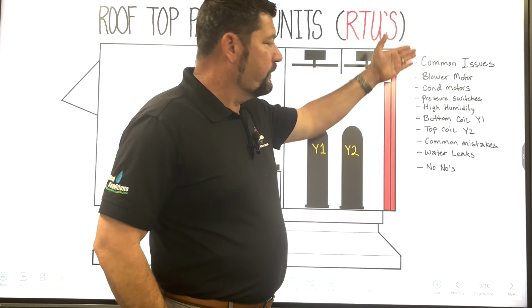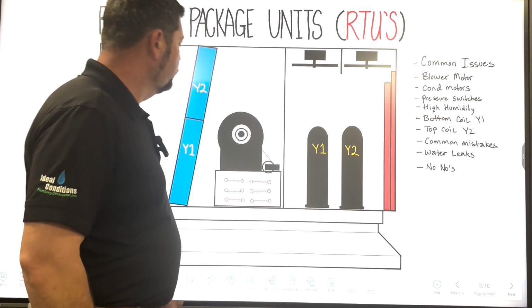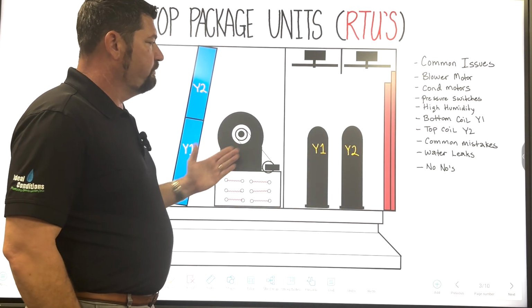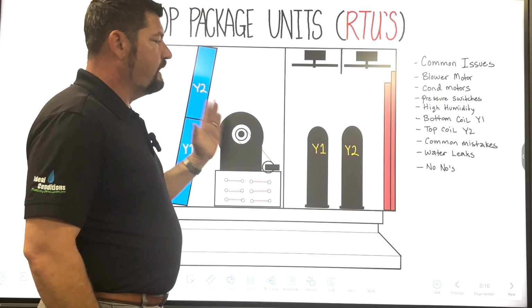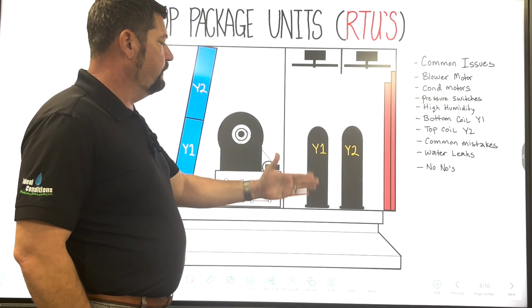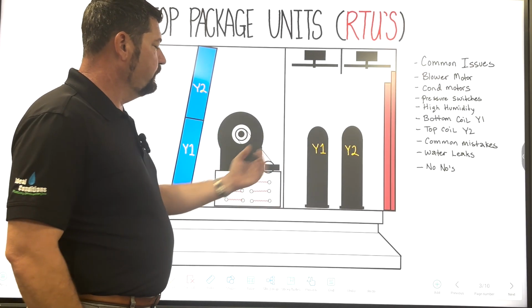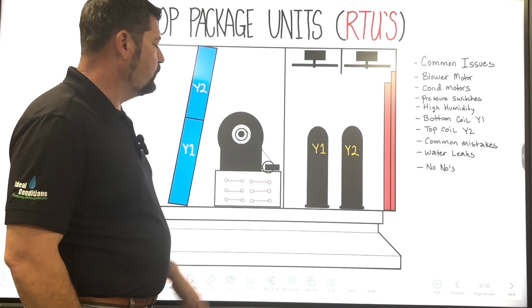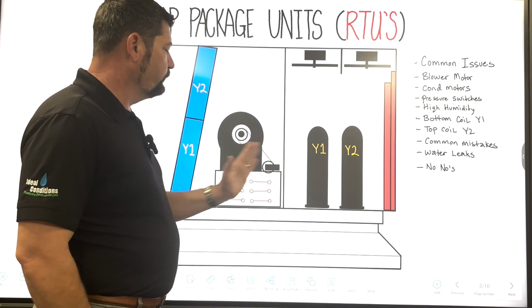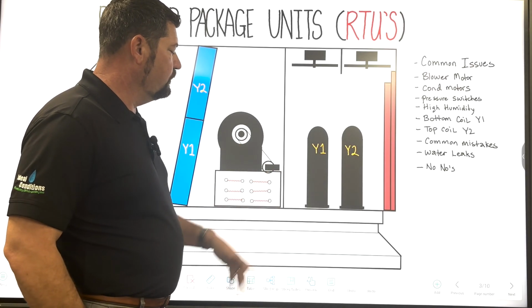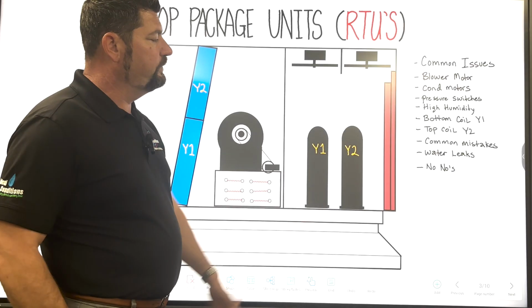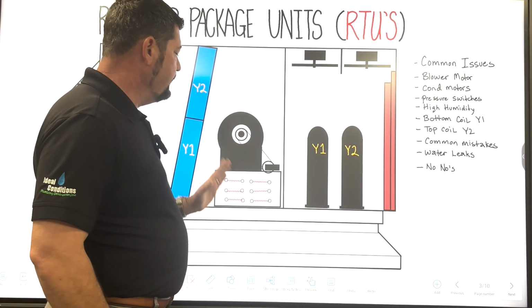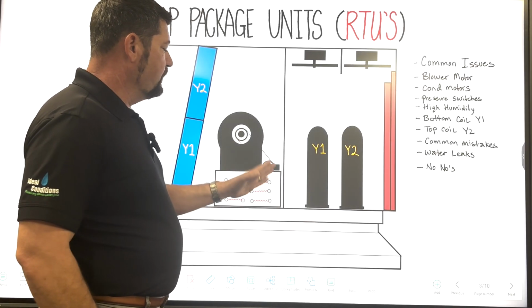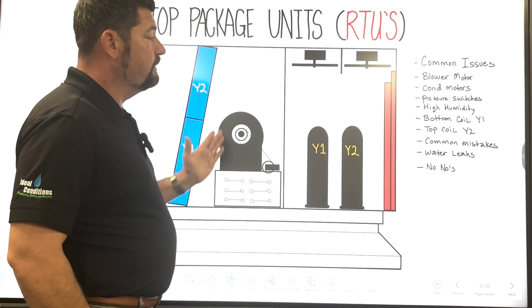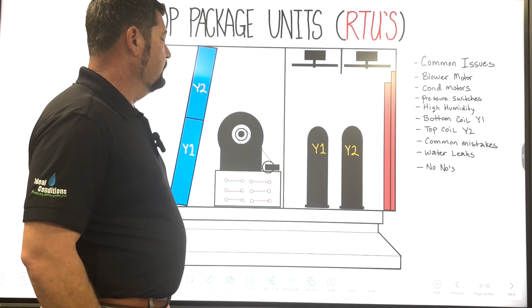Getting right into other things, the blower motors. If you have to replace a blower motor, you don't have to go back with factory motors. You can go with an aftermarket motor as long as it's within the specifications and you wire the voltage correctly, whether it's high voltage or low voltage. Low voltage meaning 208, 230, high voltage 460, 480. In the event that these motors are wired wrong, you wind up having issues there.